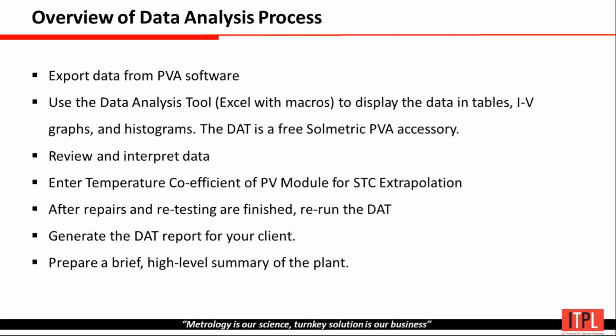What we need to do is export that complete PVA software folder into this data analysis tool. We have to put the temperature coefficient values with respect to current, voltage and power, and it will give us all the parameters, including the measured value, the STC values, the performance level, and the predicted values, along with the IV curve, power curve and STC curve. We get all of this in one complete PDF file.